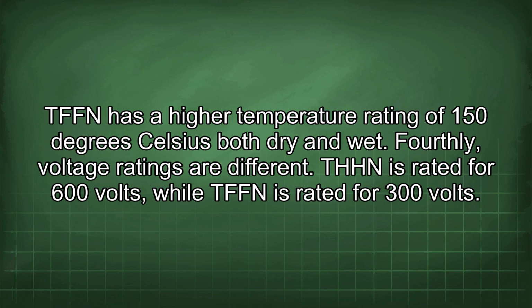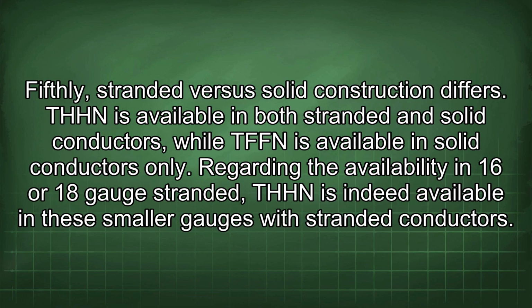Fourthly, voltage ratings are different. THHN is rated for 600 volts, while TFFN is rated for 300 volts. Fifthly, stranded versus solid construction differs. THHN is available in both stranded and solid conductors, while TFFN is available in solid conductors only. Regarding the availability in 16 or 18 gauge stranded, THHN is indeed available in these smaller gauges with stranded conductors.